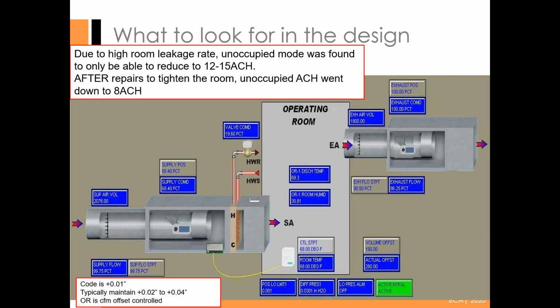And this has a lot of information on it. Pretty much it was the end result of what happens when they didn't. The room, we weren't able to dial back to unoccupied mode. And we're at 20 air changes per hour on this. And when you unoccupy, there's no real required air changes. Basically, you have to maintain pressure, and you can maintain temperature, humidity, whatever, but you don't have to have the air changes because there's no operating going on in there. But we're only able to dial it back to 12 to 15, so that's a lot of energy waste.